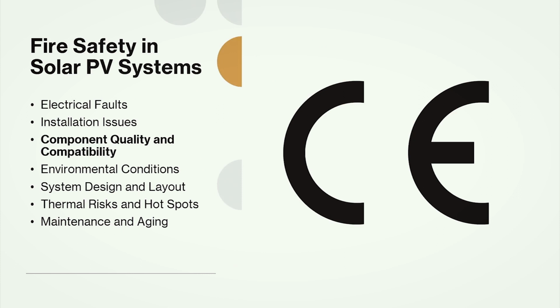Quality of components, I would say we should be using reliable, trustworthy manufacturers and suppliers. We look for the CE mark so we know that components are good quality, that the cables, switchgear, surge protective devices, and inverters are good quality. And we have to be careful about compatibility. For example, DC connectors, which are often referred to as MC4 connectors, since the largest manufacturer calls them that, are often used from different manufacturers, and they are not designed to work together. Those are part of those failures we discussed before. Again, supervision and use of correct IP rating devices as well.